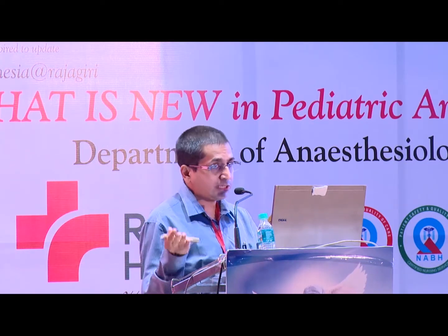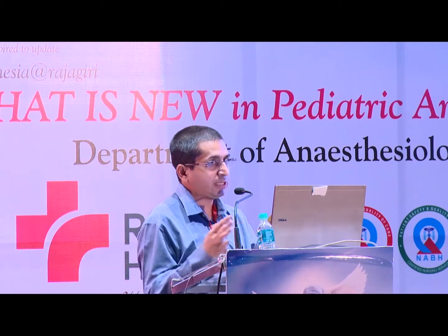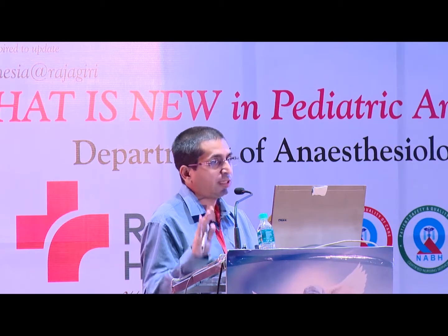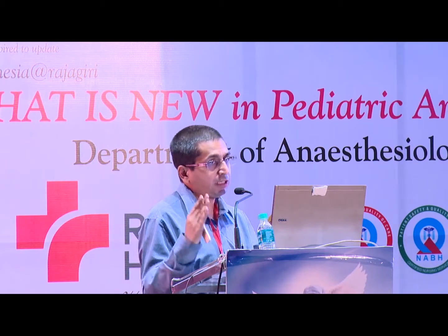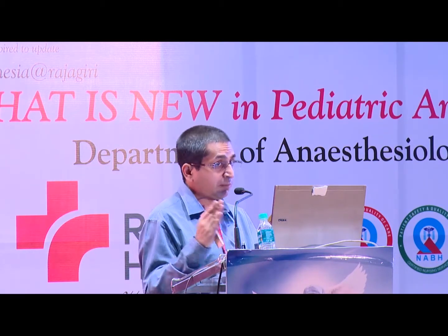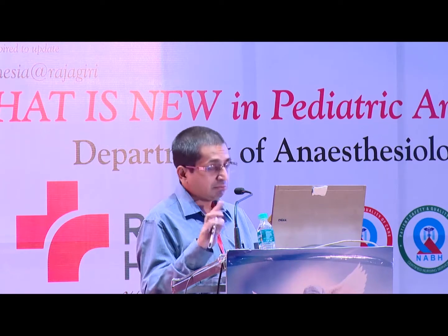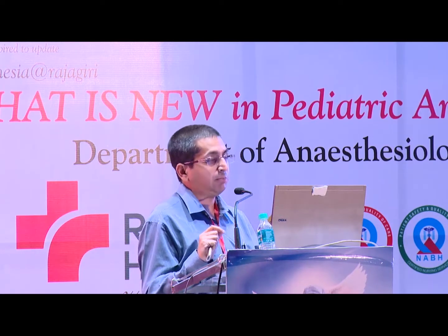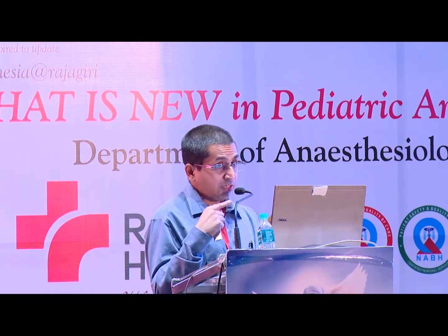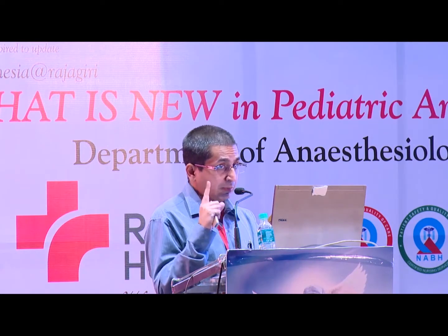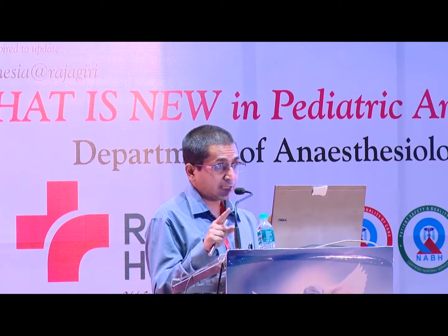If the saturation reads 70, it's not 70, because the pulse oximeter is not calibrated to read 70. The usual operating ranges for most pulse oximeters are 81 to 100 with an error of plus or minus 2 or 3. So technical literature is important. What about cerebral saturations? This is not evidence based. When you are in trouble, remember the crux is cerebral blood supply.